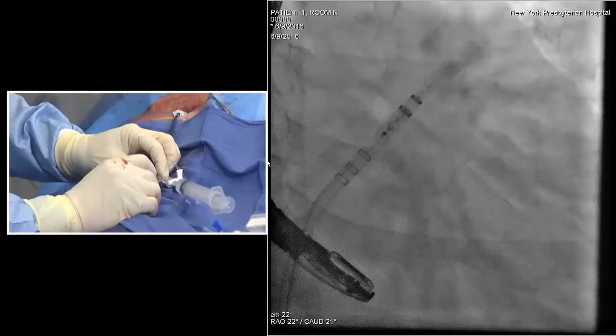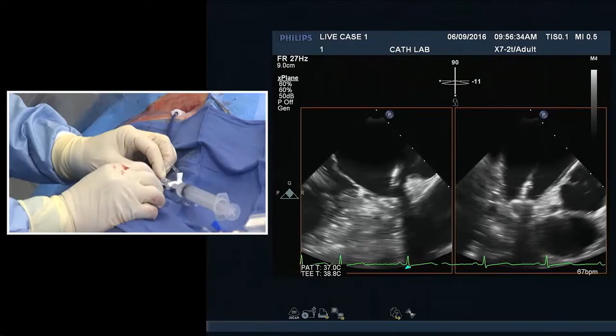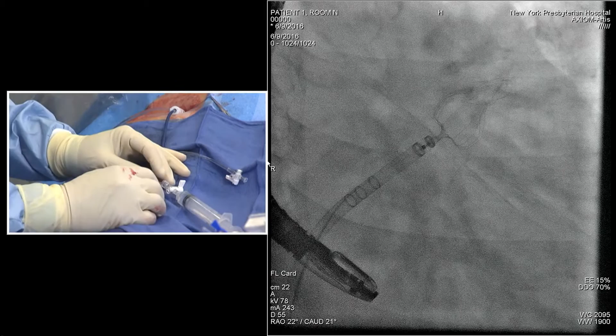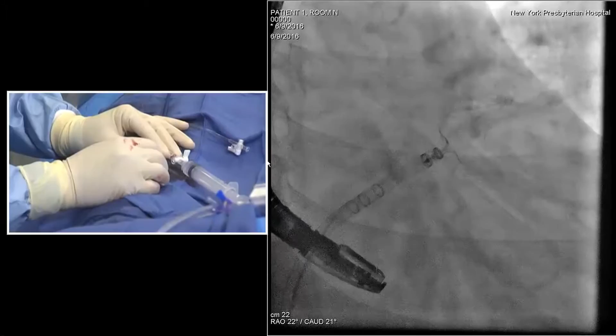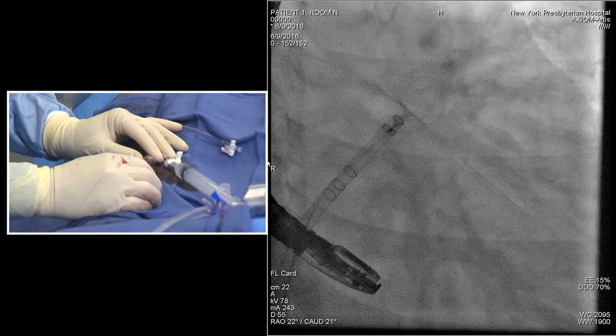Correct. You can see the feet starting to spread. And it's going to pop open here in a second. Okay. Okay, now what you see here, and Becky will show us this on the echo in a second, but you can see how the distal feet are all still compressed. And that's going to leave you with a device that's not fully open to its full diameter. Now, sometimes if you use a large enough device, that's not a problem. But if you need this thing to open up fully, and we're going to look at the echo now in a second, we may need to redeploy this a millimeter or so more proximal. Becky, why don't you see what this looks like?